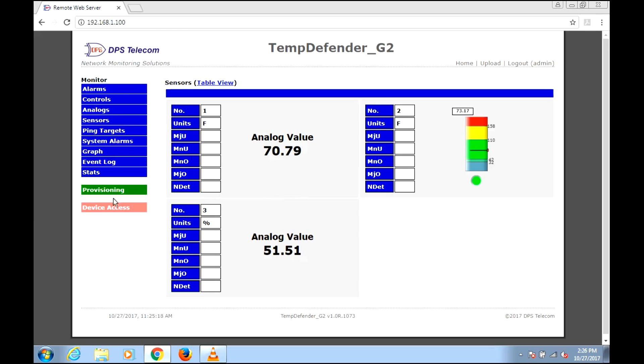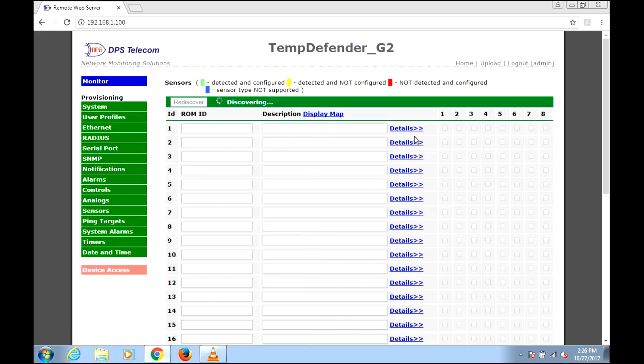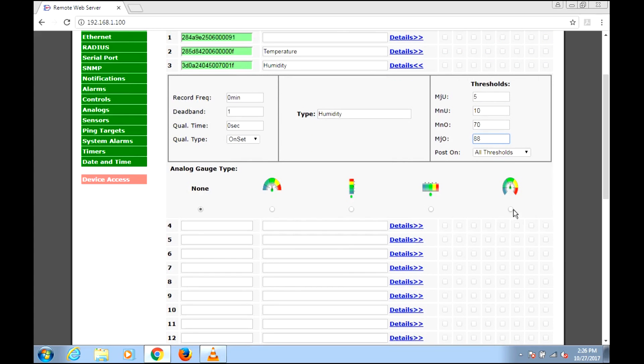Let's go back and configure humidity. I'm going to label the first one 'Temperature' and label this one 'Humidity.' The default thresholds aren't appropriate for humidity — those are more like what you'd use for temperature. So let's set a low threshold at 5 (concerned about arcing and static), 10 for minor, minor at 70, and a major at 88. For the gauge I'll go with something that looks like a hygrometer — this arc one here. Just use whatever makes the most sense to you.